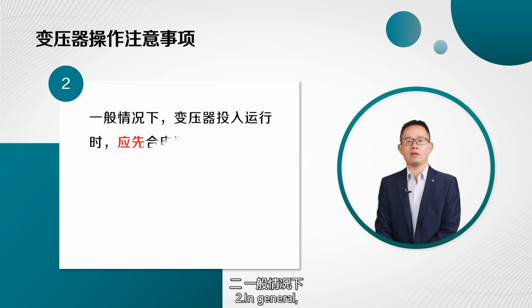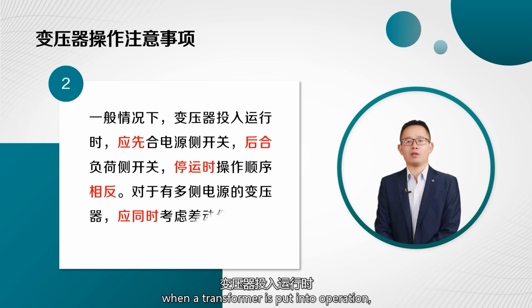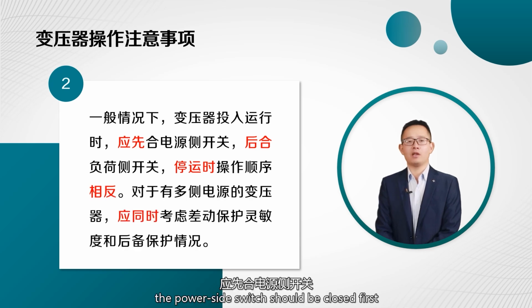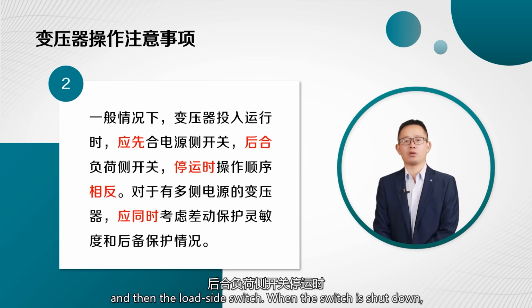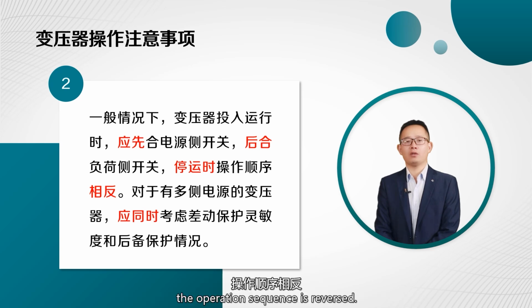Second, in general, when the transformer is put into operation, the power side switch should be closed first, and then the load side switch. When the switch is shut down, the operation sequence is reversed. For transformers with multiple power sources, differential protection, sensitivity, and backup protection should be considered simultaneously.